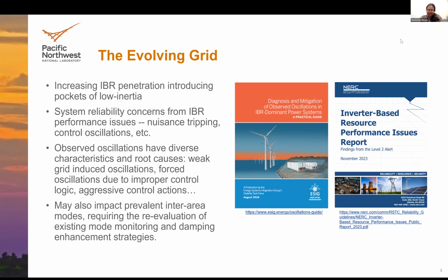So the observed oscillations that are being reported today have diverse characteristics and root causes. There are subsynchronous oscillations arising due to interaction between inverters and, say, wind turbines or other grid elements. For example, there have been oscillations reported when wind turbines have been left connected radially to a series compensated line. Then there are forced oscillations that are arising due to improper control logic. Sometimes, something we would call low tech: the units are fine, but maybe the plant control logic is providing erroneous time constants or erroneous reference commands to the individual plants, which is causing the units within a plant to oscillate against each other, and that is introducing oscillations in the system.